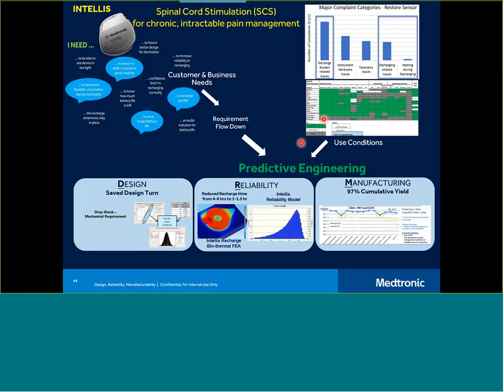So we used those inputs and our requirement flow down in predictive engineering. On the design side, we made sure we met a mechanical requirement of being able to hold up when dropped and everything else, and a reliability requirement as well. On the reliability side, though, we reduced that recharge time from the predicate product's 4 to 6 hours to about an hour. And we did a biothermal analysis to make sure that the faster recharge would not cause any harm to the patient over the range of use conditions. And then we built an Intellis reliability model that helped with the reliability, and that was a Bayesian model, which I'll show a little bit about on a coming up slide.